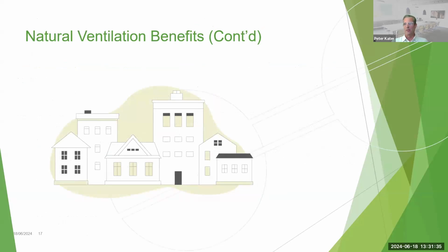So this diagram is really just highlighting some of the benefits that you can get with natural ventilation in public buildings. Night cooling I've mentioned before, which is where you pre-cool the interior of the building using outside air at the coolest time of the day. And that means the mechanical ventilation system, the cooling system, doesn't have to be switched on till later in the day. This is especially applicable in warmer climates where you can't necessarily operate natural ventilation during the hottest part of the day.